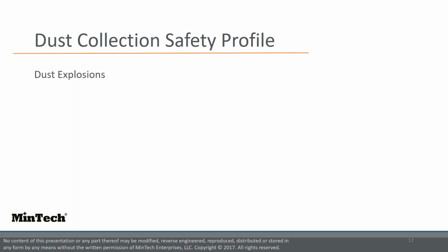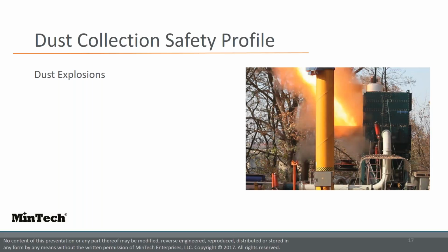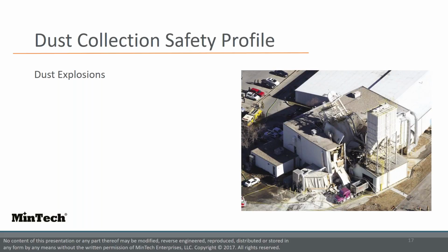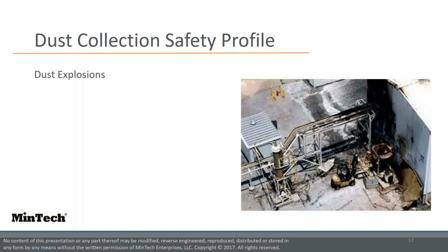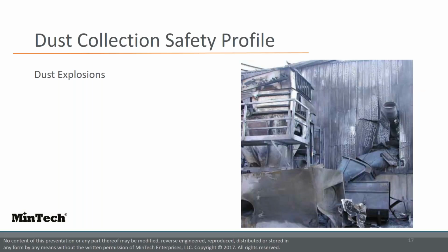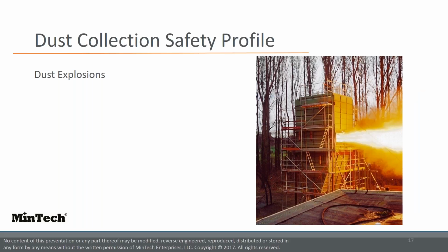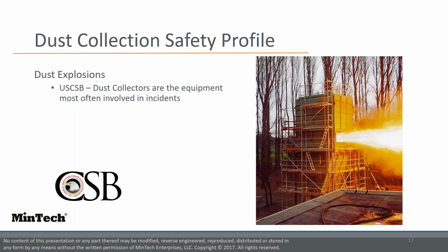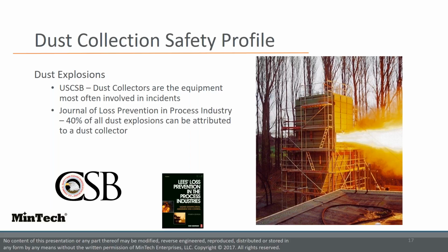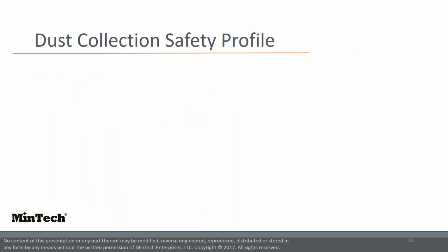While dust collection does improve the overall safety of a facility or process, there are inherent safety concerns due to the general concept of their design. It's no secret that dust collectors often explode. This makes sense if you think about it, because you're essentially gathering dust fines, transferring them with high volumes of air through ductwork into a gathering area. The U.S. Chemical Safety Board found that in all industries, dust collectors are the equipment most often involved with incidents. Grinders, silos, hoppers, and mixers are also involved in numerous incidents. Similarly, an article in the Journal of Loss Prevention in the Process Industries reported that 40% of all dust explosions can be attributed to a dust collector.